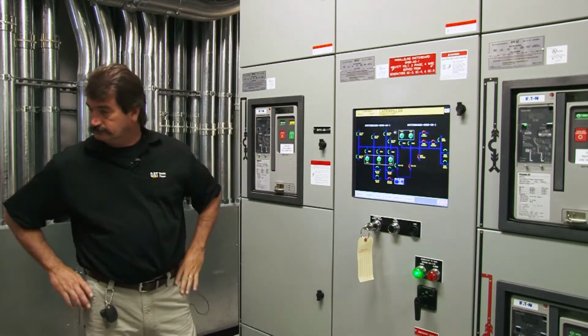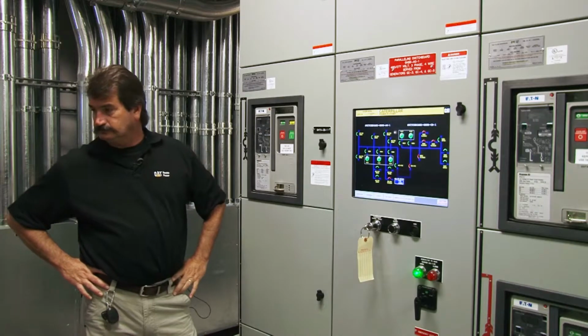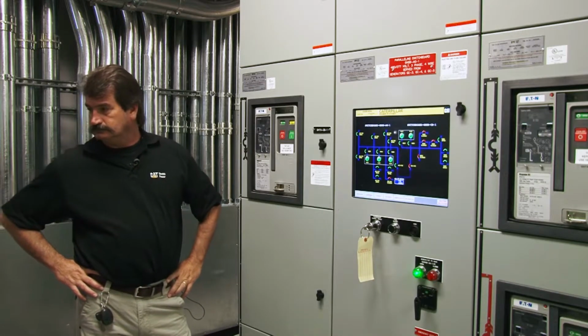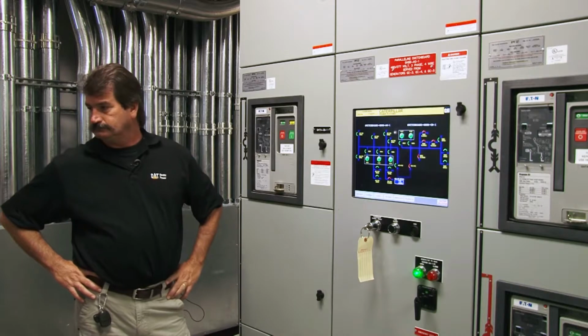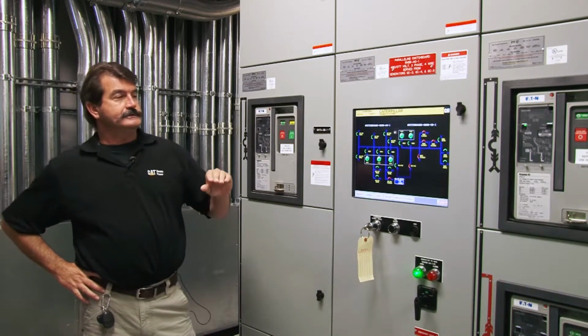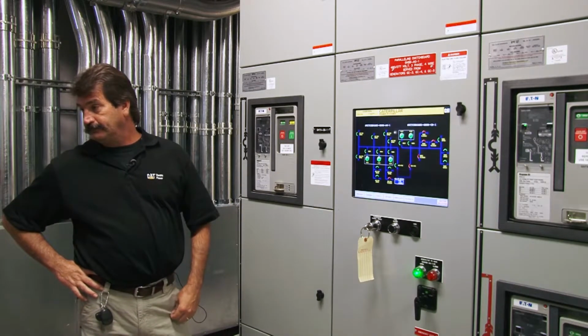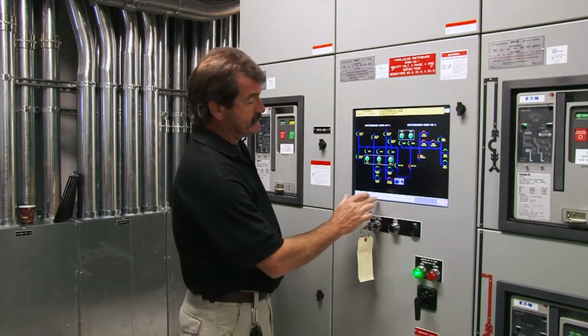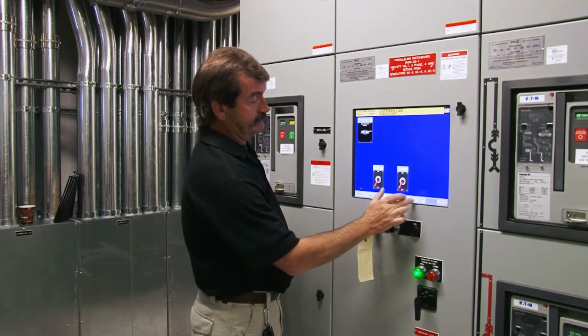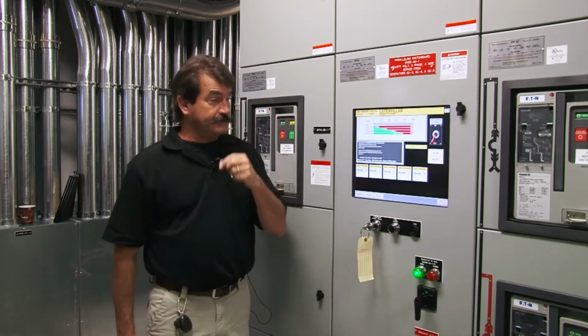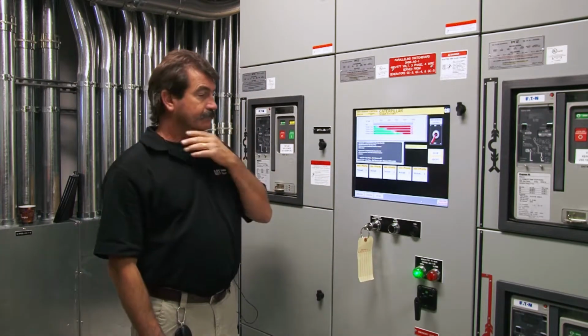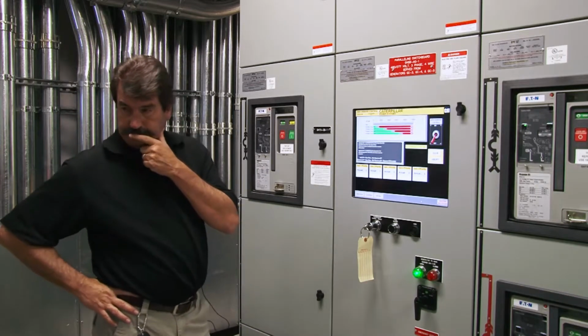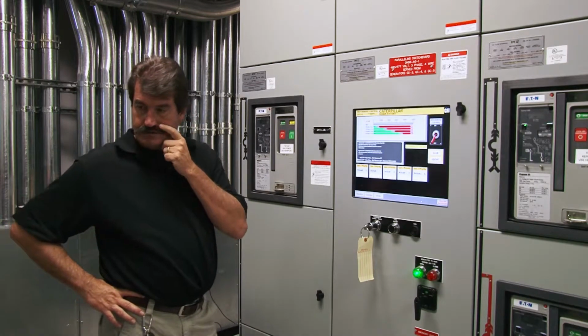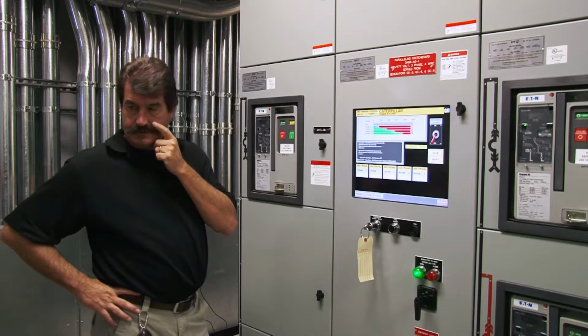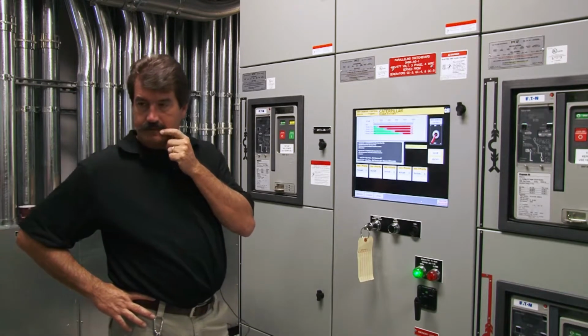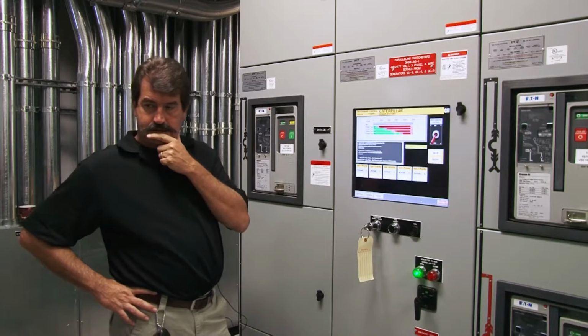The old generator gen sets we had in here, if we didn't have enough load, one of them would shut down, and we'd run it in manual. Does that do the same thing here? You do, but it's turned off at this point. That is this gen demand right here. Yeah, we went through that when we ran the facility. And when it was shutting engines down, it was opening breakers, bouncing the facility back and forth. Rather than save fuel, I'd rather burn the fuel.